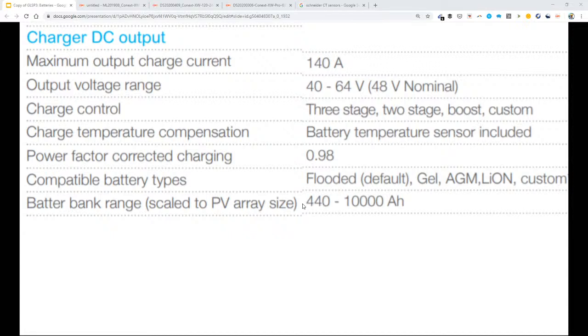Here's a side. There's the side that deals with outputting to the grid, and then there's the side that deals with charging from the grid into the battery. So it's telling us that there might be a difference between the charge rate of the batteries and the discharge rate from the inverter. More importantly, it's telling us the voltage range of these batteries, and that's important because there's a lot of 48 volt stuff out there, and not all residential batteries are 48 volts. Some are much higher than that. We're going to talk about that in a minute.